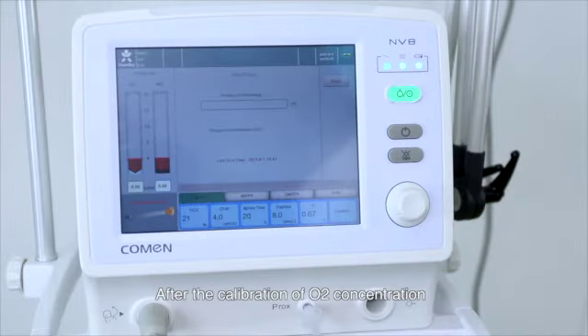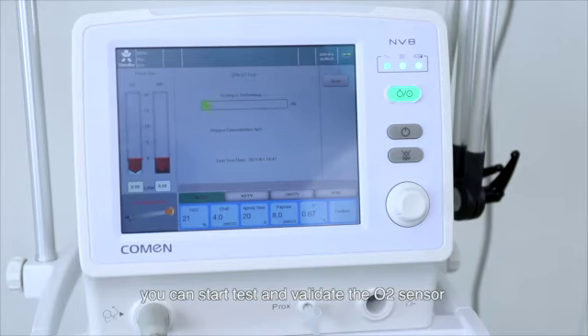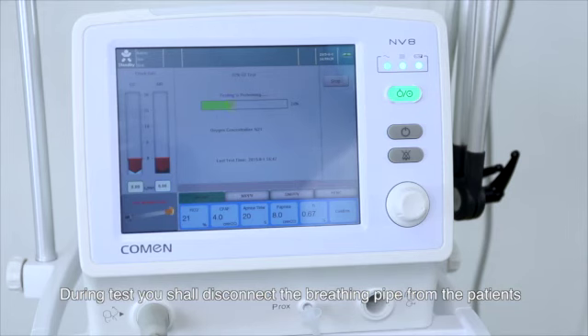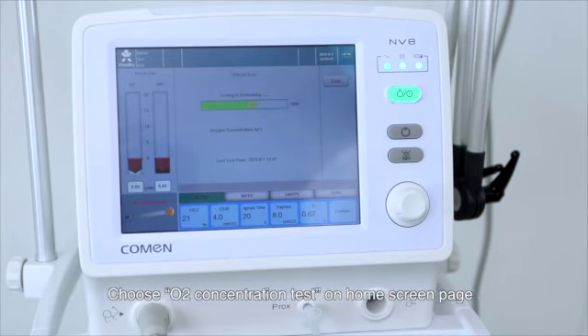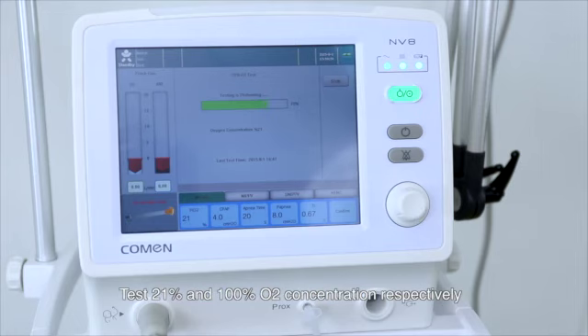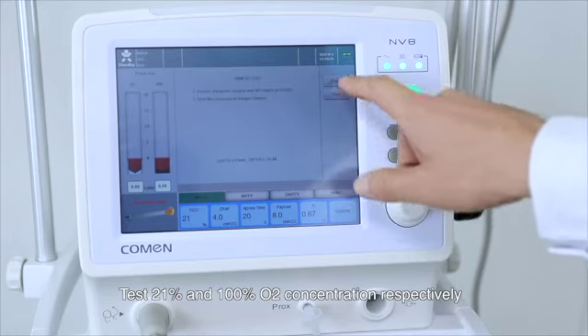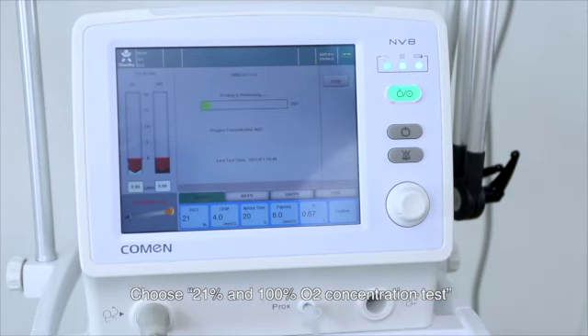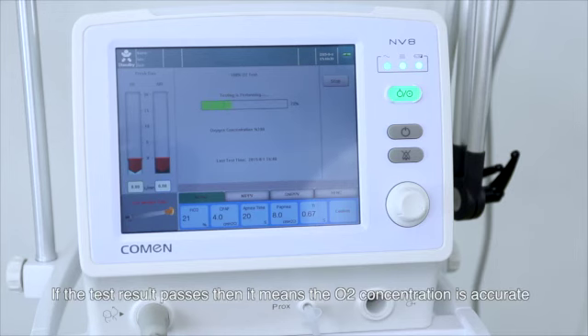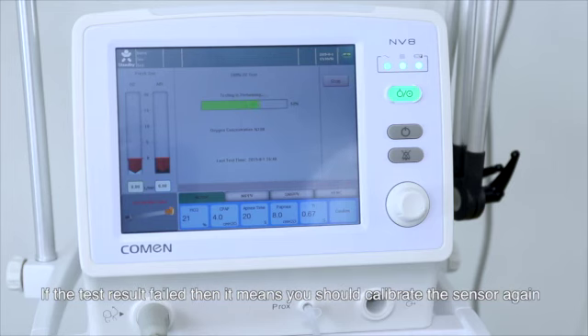Oxygen concentration test. After the calibration of oxygen concentration, you can start test and validate the oxygen sensor. During test, you shall disconnect the breathing pipe from the patients. Choose oxygen concentration test on home screen page. Test 21% and 100% oxygen respectively. Choose 21% and 100% oxygen concentration test. If the test result passes, then it means the oxygen concentration is accurate. If the test result failed, then it means you should calibrate the sensor again.